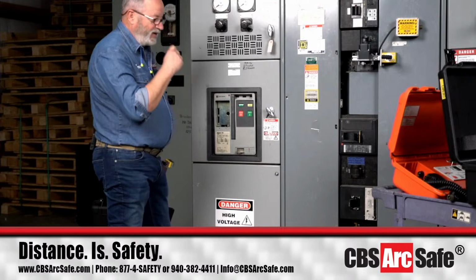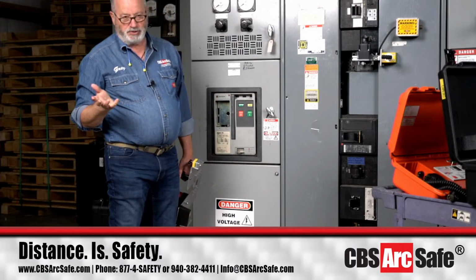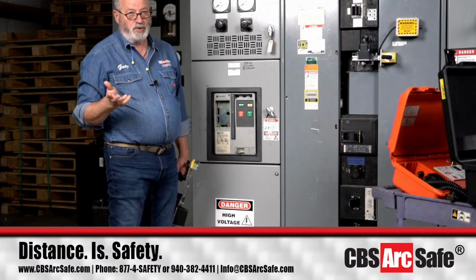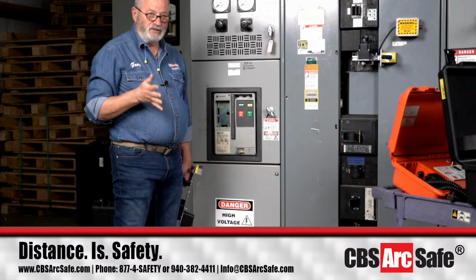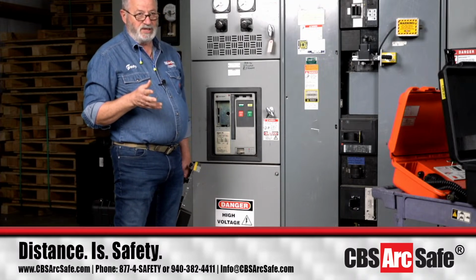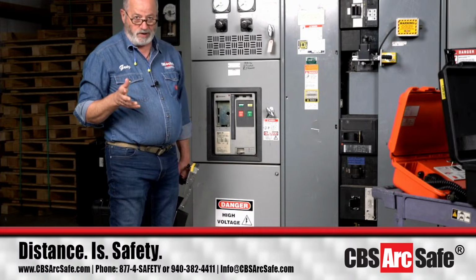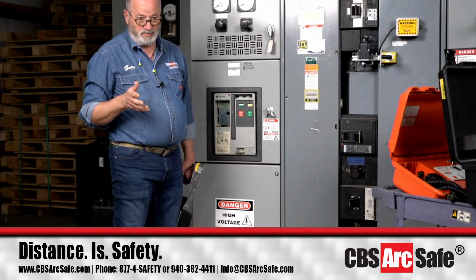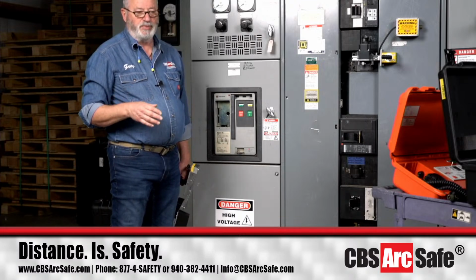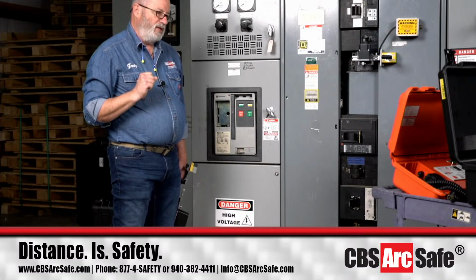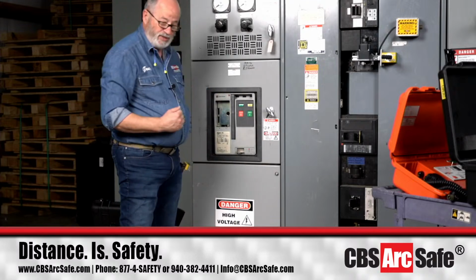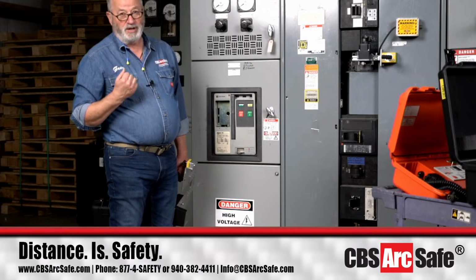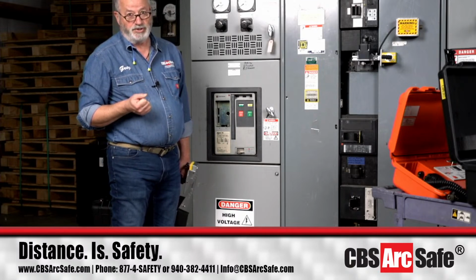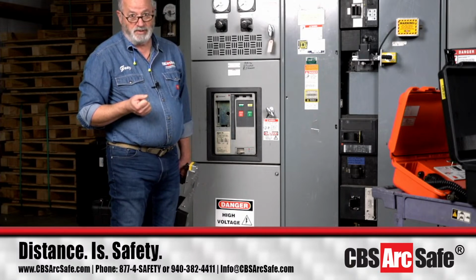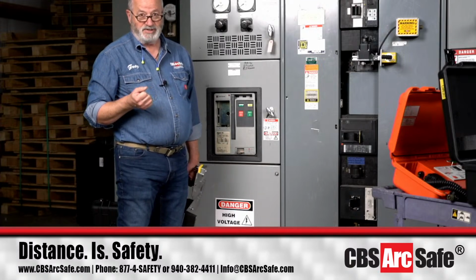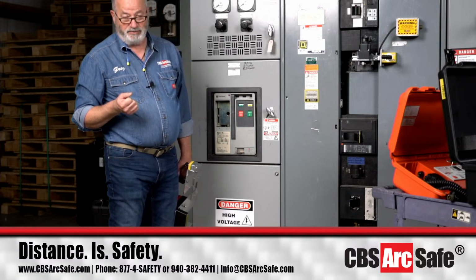And sometimes people ask us, well, do I really have to have a charge close trip system? And what I will tell you is that I've seen on other types of insulated case breakers that have been worn heavily, I've seen this in the Middle East on the first generation Emax breakers, if this charging system gets worn, that breaker can close at the bottom of the last charging stroke. Okay, I've had that happen in some of the facilities I've done demonstrations and training on over there.